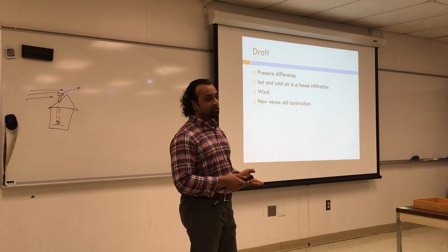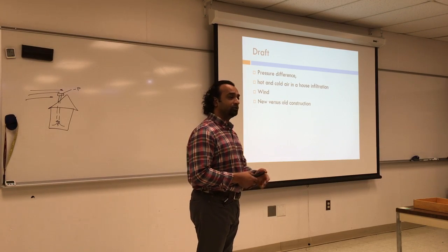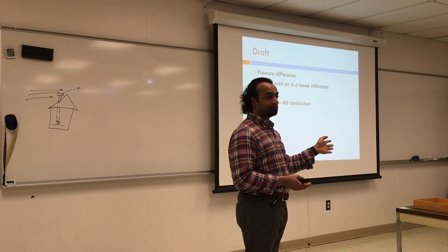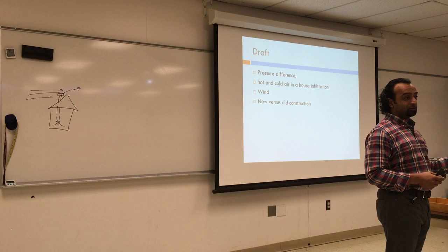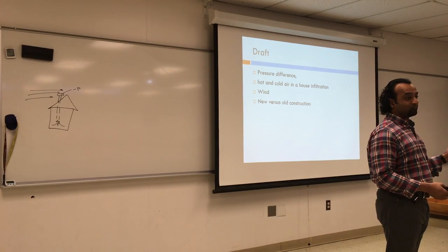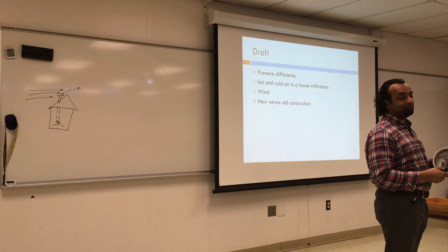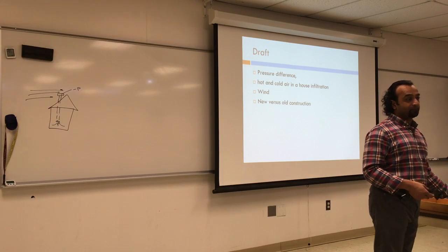It's better if you have your own incoming air from the outside, and your flue pipe goes to the outside, induced. Granted that you have one of these in your vent. Otherwise, you're going to pull too much air from the chamber. But if you have this, again, you're going to have to have some makeup air. So you have to open something in the room to let the air in.